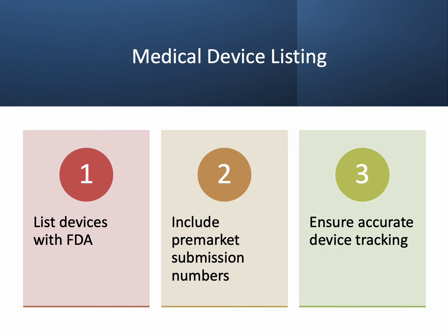Following establishment registration, let's explore medical device listing in U.S. regulation. Establishments required to register with the FDA must also list their devices, detailing the devices made and activities performed, e.g., manufacturing, repackaging. If a device requires pre-market submission, e.g., 510(k), the owner-operator must provide the submission number.